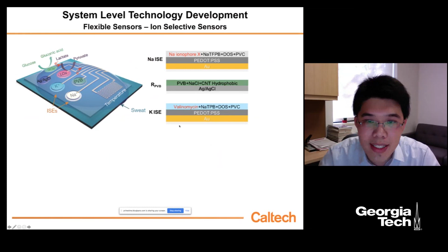potassium, potassium will go into this ring and set the voltage of this working electrode. According to the Nernst equation, we are actually measuring the voltage difference between the working and the reference electrode. So the measured voltage is proportional to the logarithm of the ion concentration. If we are measuring sodium and potassium, the charge of the ion equals 1, and the slope is 59.16 millivolts per decade of concentration. So remember, for glucose and lactate, the response is linear. For these ions, it is a logarithm of the concentration. The slope is 59 millivolts per decade. And if we are measuring calcium or magnesium, for example, Z equals 2, and the slope or sensitivity becomes 29.6 millivolts per decade of concentration.